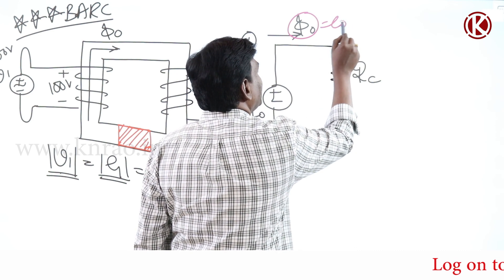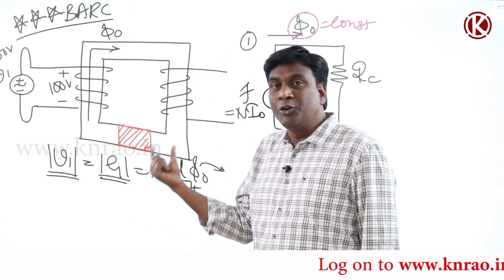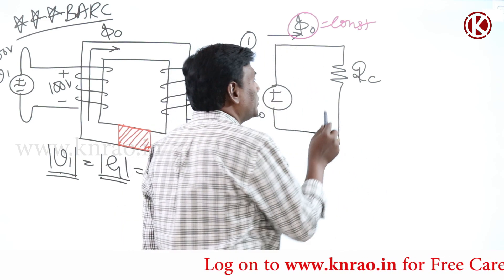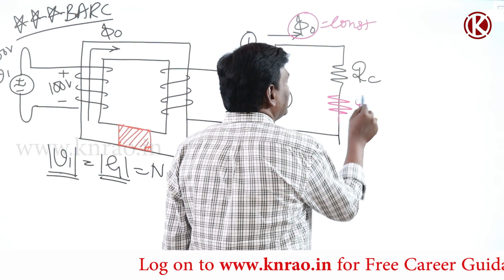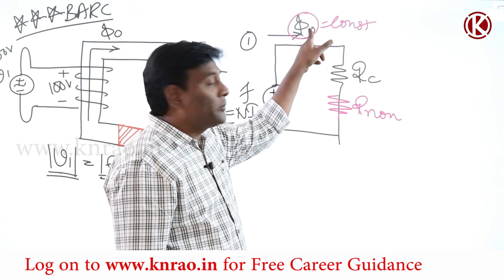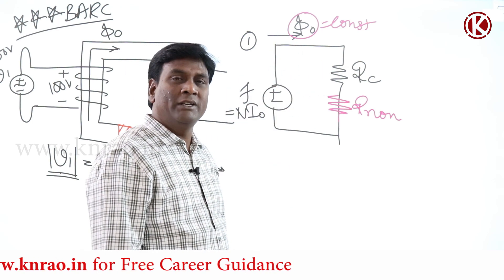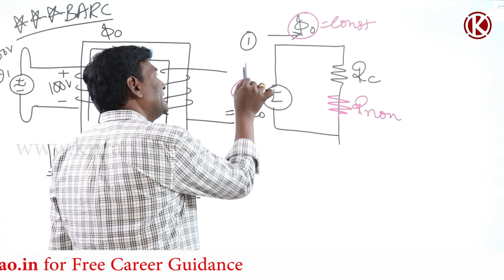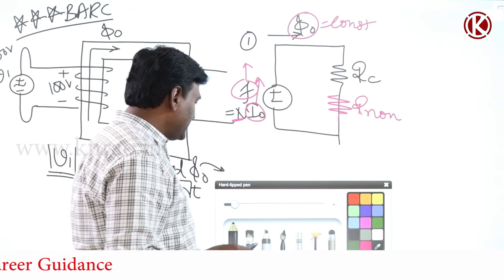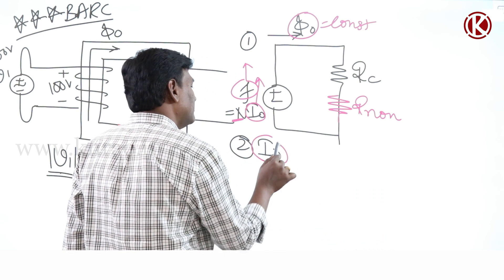In the second case (red), the operating flux remains constant. But some part of the magnetic material has been removed and filled with non-magnetic material, whose relative permeability is only one — so reluctance is going to be high. The reluctance of the non-magnetic material is added. Since operating flux must be the same but resistance has increased, by analogy the MMF must increase. Number of turns is the same, so the no-load current has to increase. That is the second point.